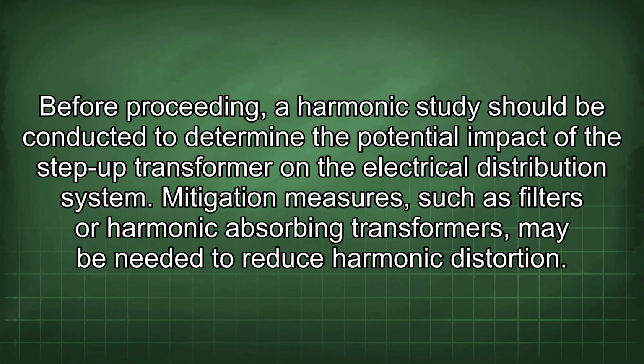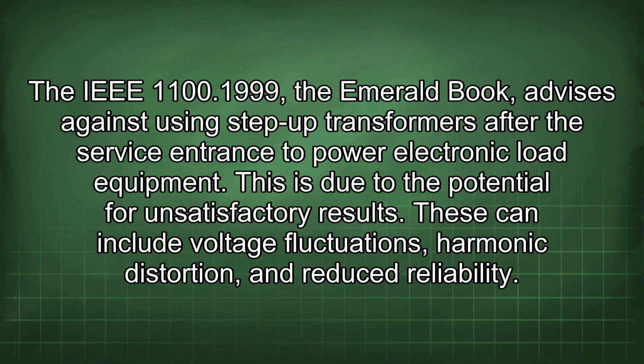Before proceeding, a harmonic study should be conducted to determine the potential impact of the step-up transformer on the electrical distribution system. Mitigation measures such as filters or harmonic absorbing transformers may be needed to reduce harmonic distortion. The IEEE 1100-1999, the Emerald Book, advises against using step-up transformers after the service entrance to power electronic load equipment. This is due to the potential for unsatisfactory results. These can include voltage fluctuations, harmonic distortion, and reduced reliability.